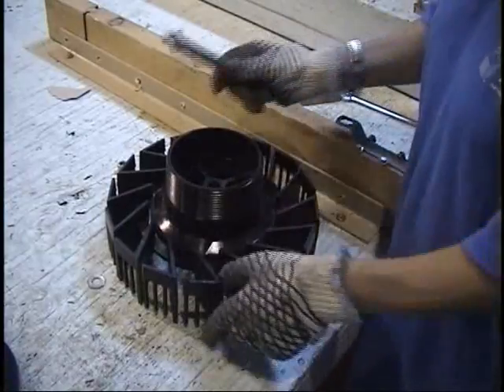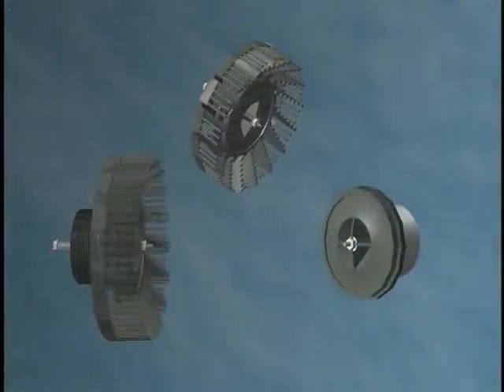The rotary spray nozzle also has a rotating disc that literally spins on a cushion of water. With a large 4-inch inlet orifice and the brisk rotating action of the rotor disc, any scale or debris attempting to build up in the nozzle is effectively dislodged. This innovative anti-plugging nozzle has no bearings, shafts, or other wearable parts, and thus requires virtually no maintenance.